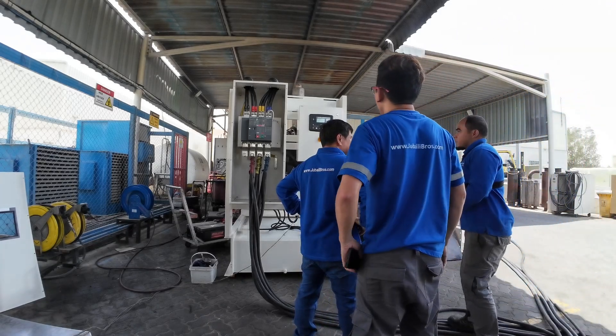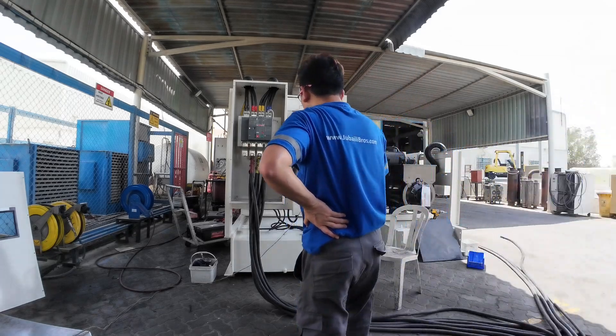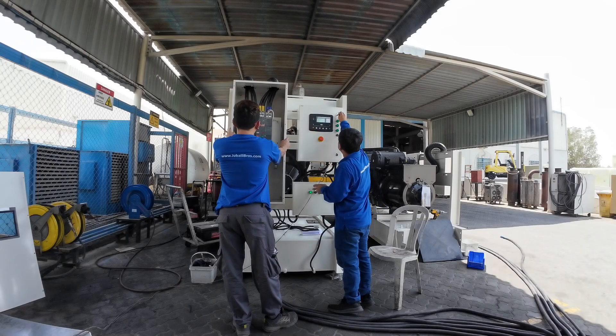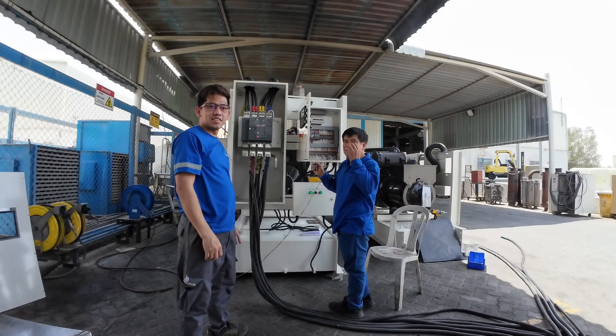At this time we have a shutdown alarm, which is an earth fault. I'm going to check the configurations and the wiring to find out why it's getting shut down, and we will change the wiring if there are any wrong connections.